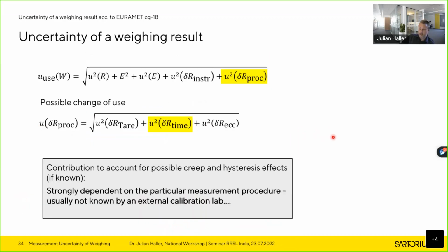And another contribution that is mentioned in the CG18, but again cannot be taken into account without deep knowledge, is, of course, possible effects of creep and hysteresis. And this, of course, strongly depends on how the user uses the balance. If you just do a simple weighing by putting something on and reading, you will usually not have creep and hysteresis. But if you do long-term measurements for whatever reason, because you need that for your application, then you might have these effects, and then they should be taken into account. But again, as this is not known, especially to external calibration labs, it just cannot be taken appropriately into account.